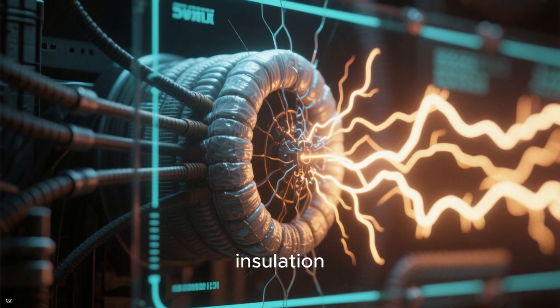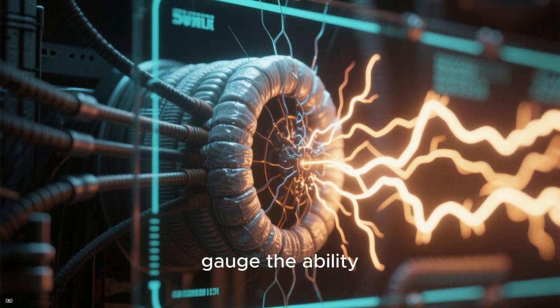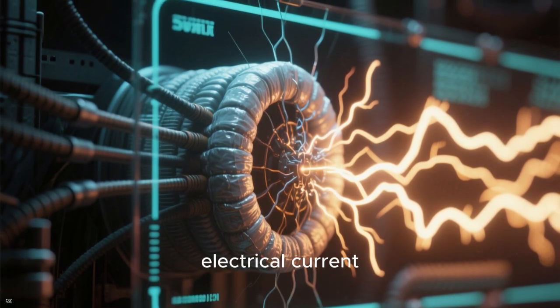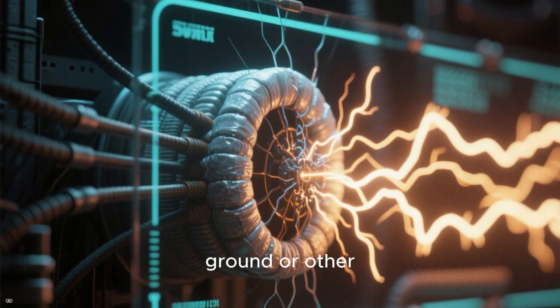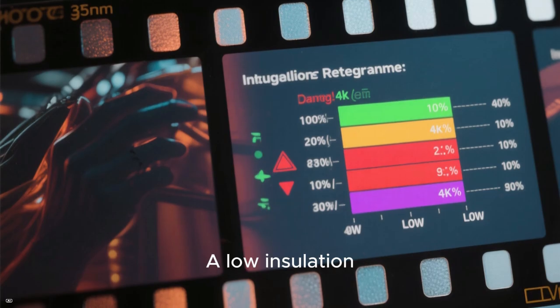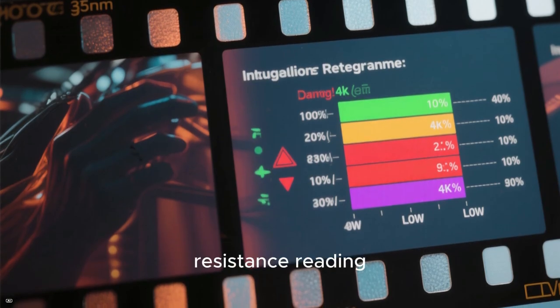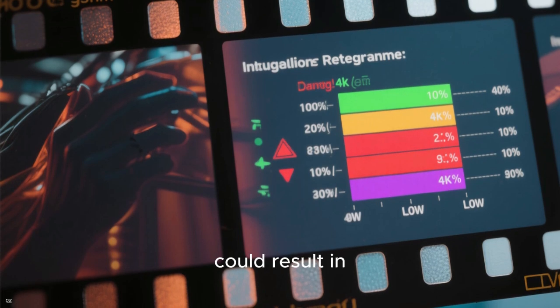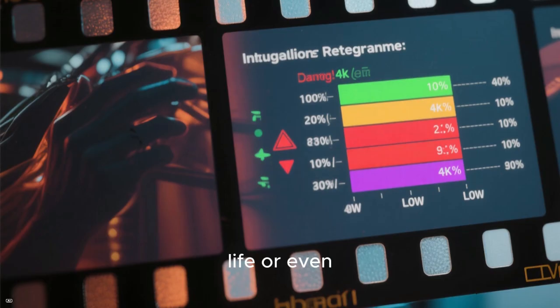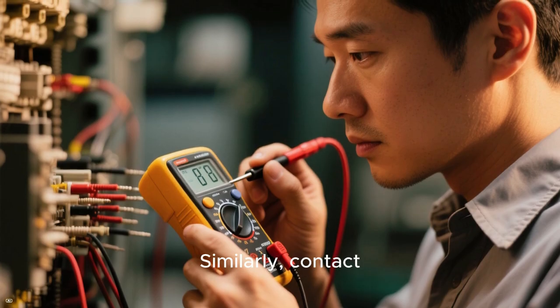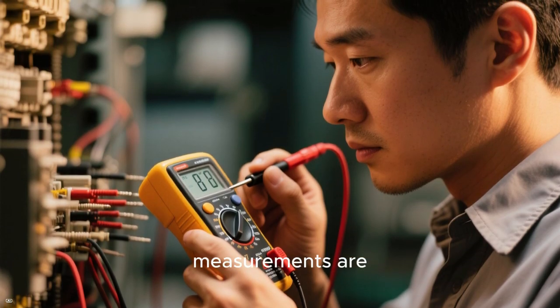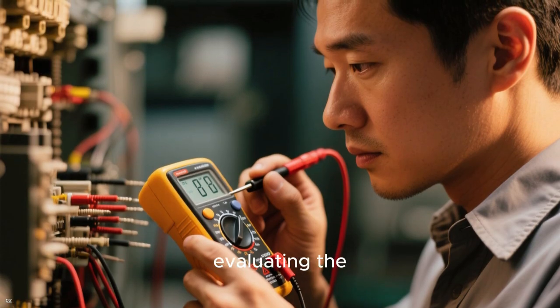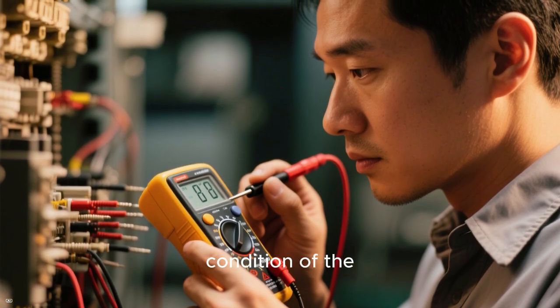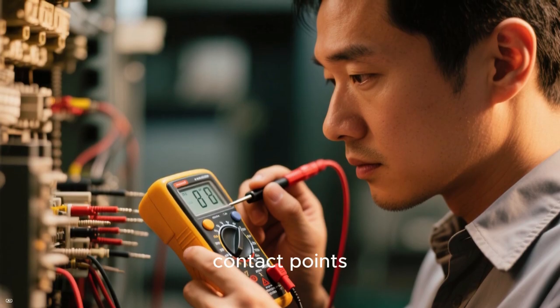By measuring the insulation resistance, we can gauge the ability of the insulation to prevent electrical current from flowing to ground or other unintended paths. A low insulation resistance reading may indicate compromised insulation, which could result in energy losses, reduced tap changer life, or even flashovers. Similarly, contact resistance measurements are vital for evaluating the connectivity and condition of the tap changer's contact points.